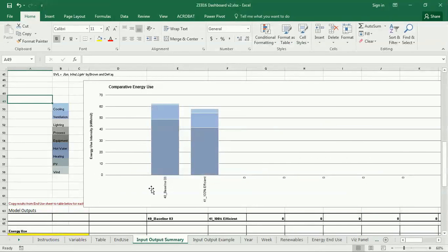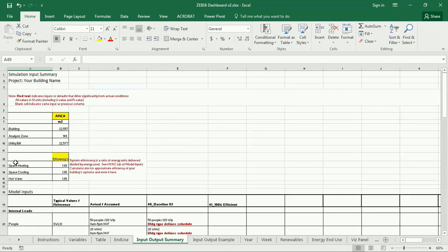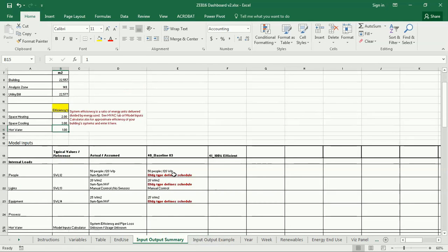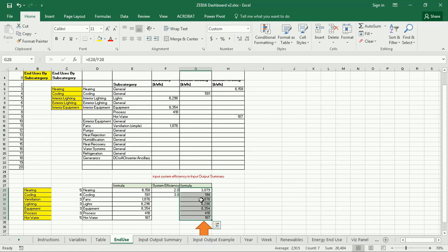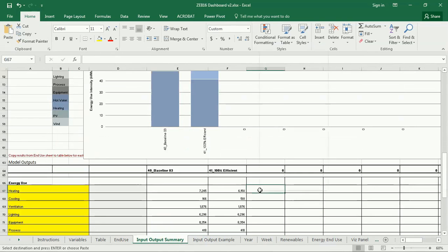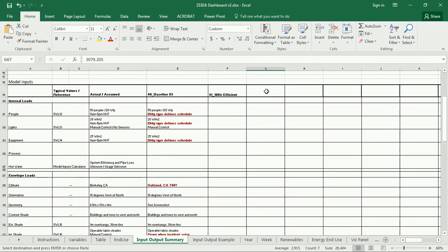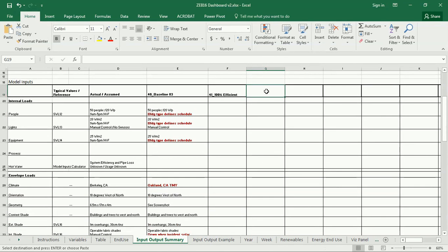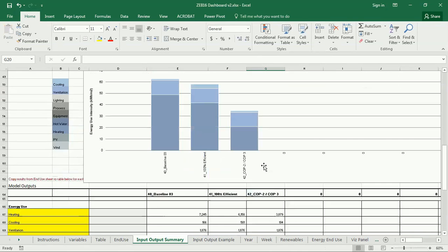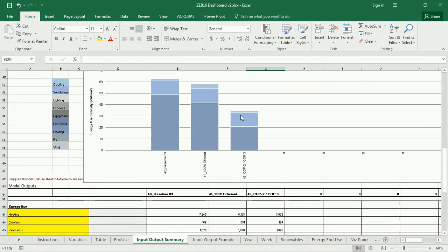So I'm going to copy these to my input output summary. And down here, I'm going to paste them. And I should have labeled this 41, 100% efficient. And you can see the difference as I've increased my cooling and decreased my heating. And in some respects, this probably makes sense to maybe just show the heating and cooling. So I'm deleting these other end uses so that we have a better sense. So I'm going to keep the heating, cooling, and ventilation. So that's the 100% efficient version. That's done. The next one is the heat pump, COP of 2 and 3. So I'm going to go to end use, or sorry, I'm going to go up to my system efficiency. The space heating heat pump would be 2, and the space cooling would be 3. If you're confused about why that is, or how that's possible, do the reading for next time, because that explains a lot about system efficiency. And so now I go back to my end use, and you'll see that these numbers have been further reduced. So I'm going to copy that over to my next column.